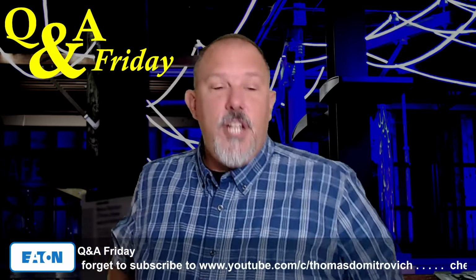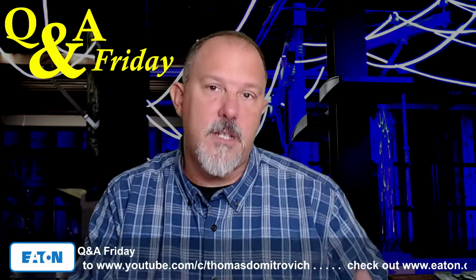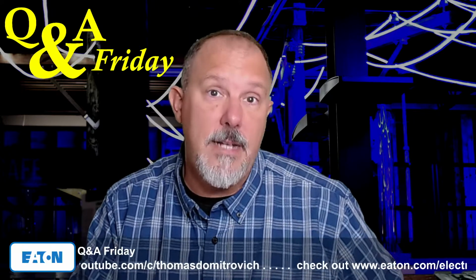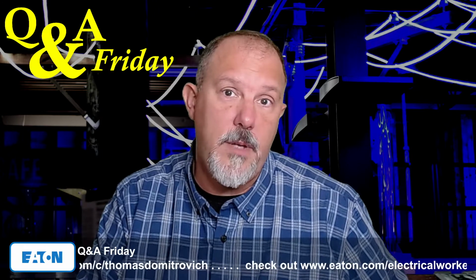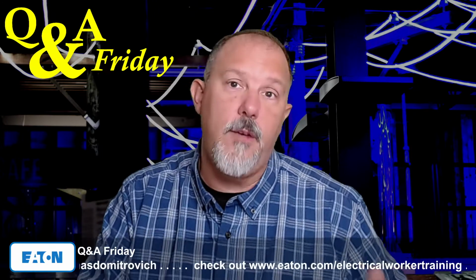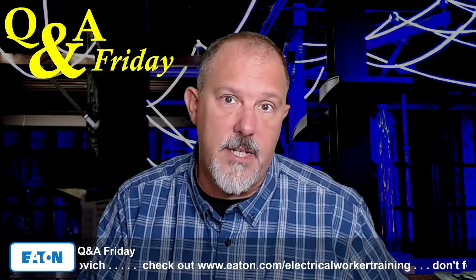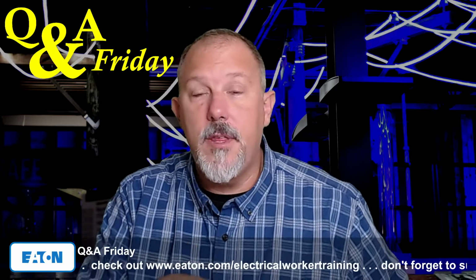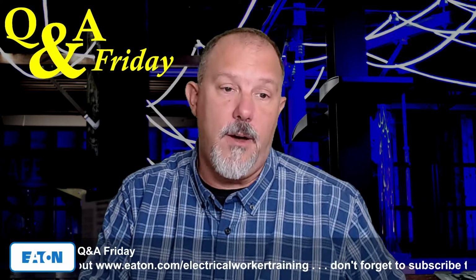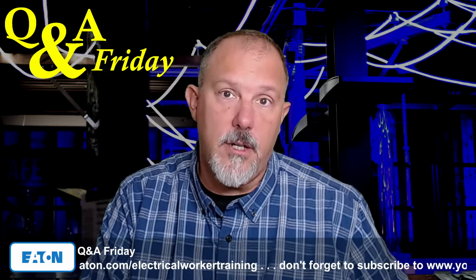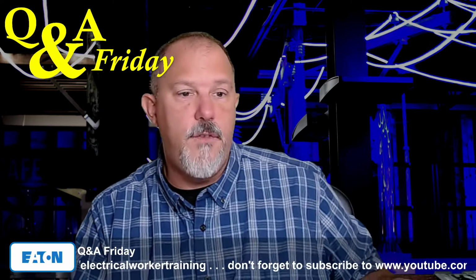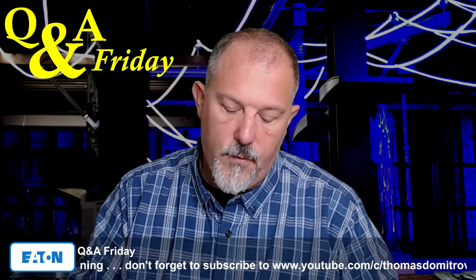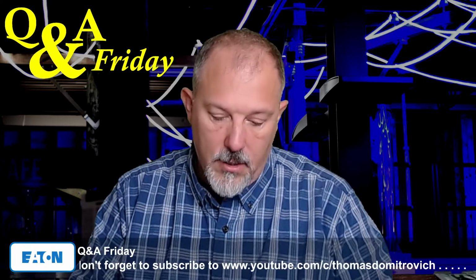All right, so JW, I would agree with you. The premise of 90.3 tells us that 1 through 4 apply generally, and 1 through 7 can modify and amend each other. But I would agree there is an effort going on right now to try to consolidate things. I'm not sure of the bunch of new requirements in medium voltage in 240. We could take a look, and I don't know if you're speaking to the 2020 code.